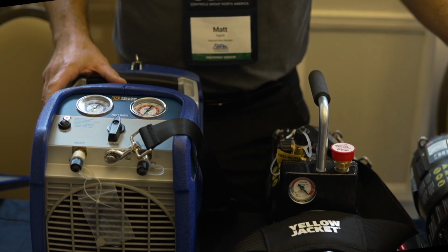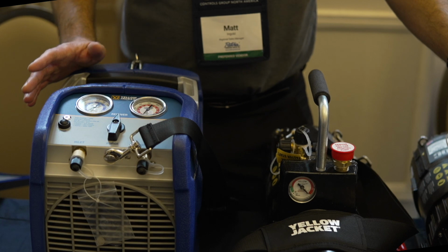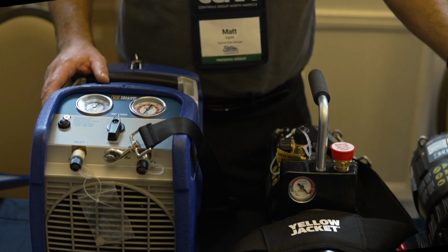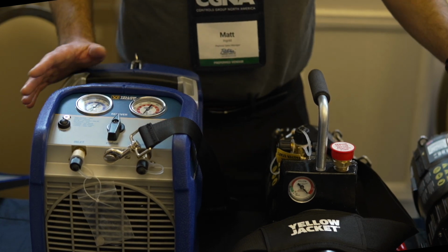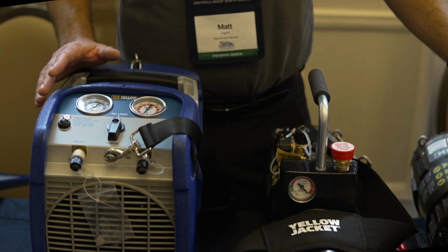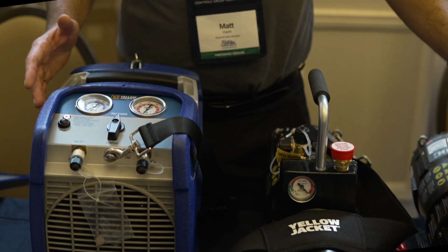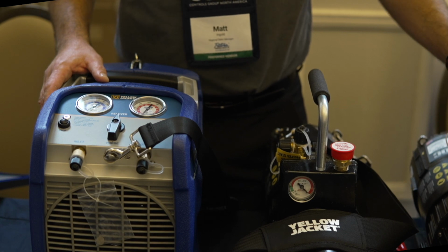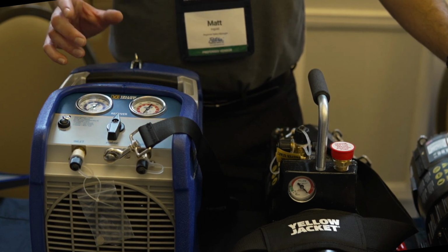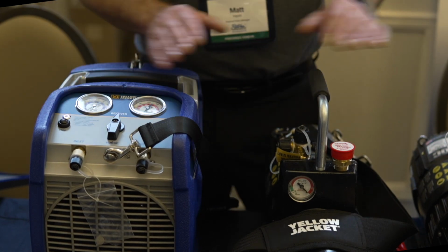Okay, well, man, you mind showing some of your products? I do not at all. Sure. So very important, there's an industry change happening with refrigerant. Right now, the most common refrigerant in new residential and commercial equipment is 410A. Come January 1, 2025, the EPA, the government, has said that 410A cannot be used in any new equipment. So all equipment manufacturers are going to A2L refrigerants, either R32 or 454B. Those refrigerants are slightly flammable, so you want to make sure that you have sparkless recovery machines and also vacuum pumps.